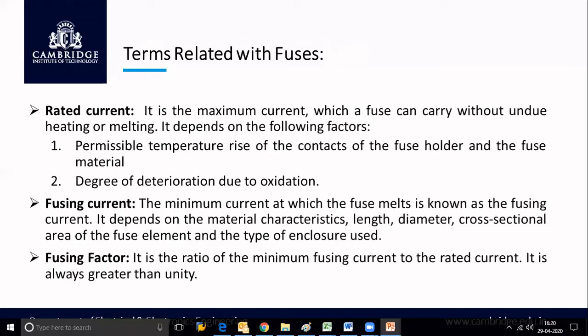Suppose the rated current of a fuse is 5 amperes, then we can select the fusing current of the fuse to be 5.5 amperes. That means when the current reaches 5.5 amperes, the fuse starts melting. So that is the minimum current at which the fuse melts. And if the current is 6 amperes or 7 amperes, that current is obviously more than the fusing current. Therefore, the fuse melts within no time. Fusing current also depends upon the material characteristics, length, diameter, cross-sectional area of the fuse element, and the type of enclosure we use. Depending on this, we determine the fusing current of a fuse.